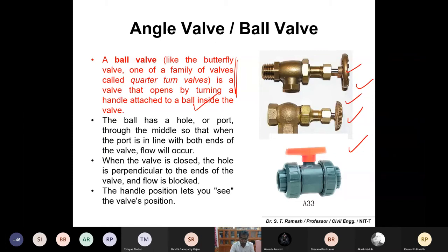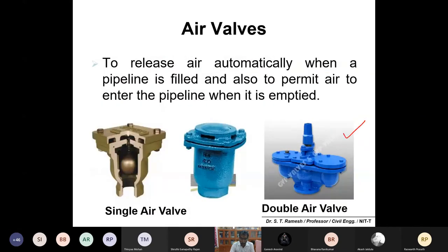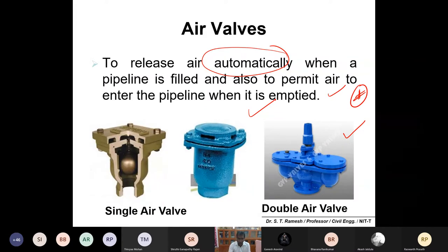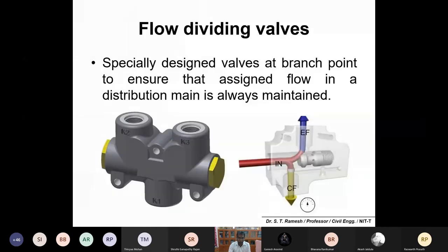Next are air valves. Sometimes water in the pipeline has higher velocity and pressure, which is more than atmospheric pressure, and sometimes air needs to be released from the water supply network. Air valves are used to release air automatically when the pipeline is filled and also to permit air to enter the pipeline when it is emptied. If you want to allow air in or release air out of the pipe, you use air valves — otherwise there could be air locks inside the pipeline.